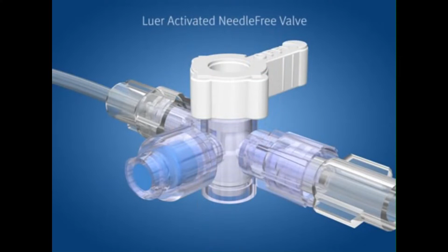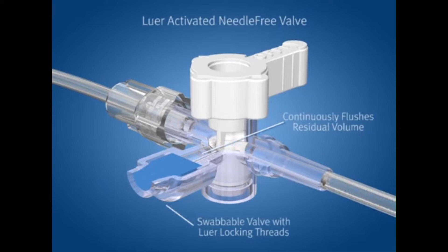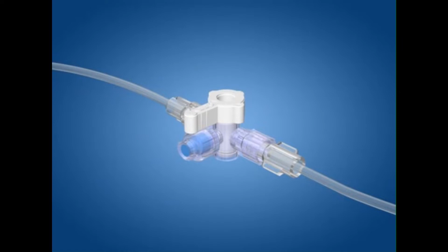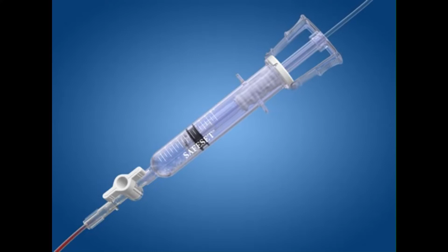Complete needle-free access to the patient's blood is provided through the use of the novel swabbable valve. This valve utilizes key design features that eliminate some of the additional steps required during the priming and flushing process when using the traditional swabbable valve for blood sampling. To access the patient's blood for sampling, first, turn the handle on the swabbable valve so that it is oriented opposite to the valve. Then aspirate the desired clearing volume into the Safeset inline reservoir.